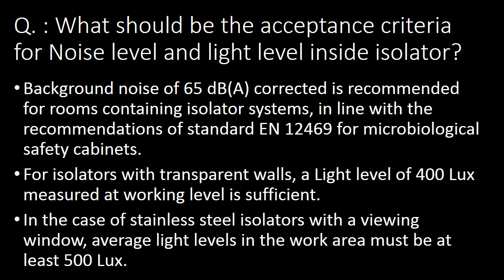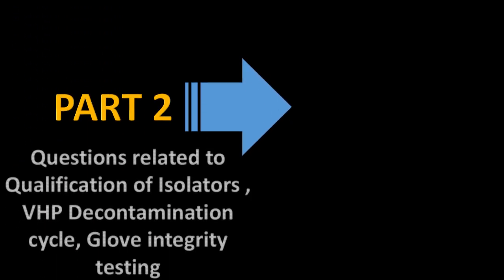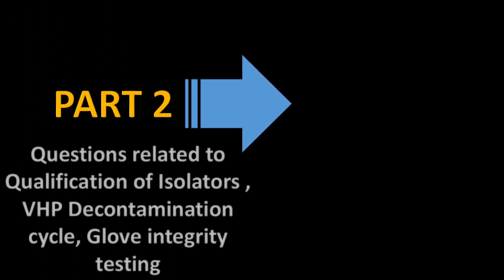For isolators with transparent walls, a light level of 400 lux measured at working level is sufficient. For stainless steel isolators with a viewing window, the average light level in the work area must be at least 500 lux.